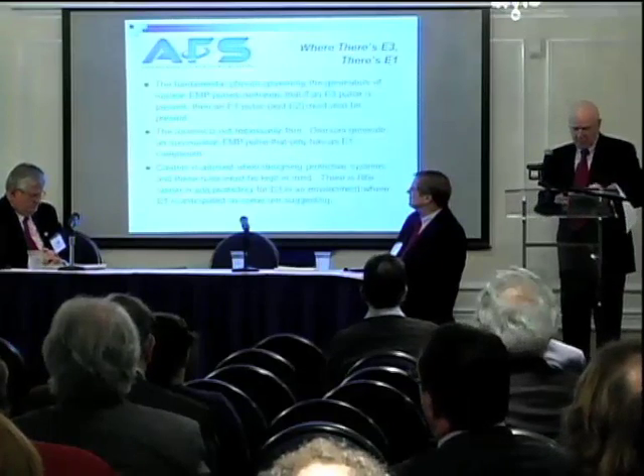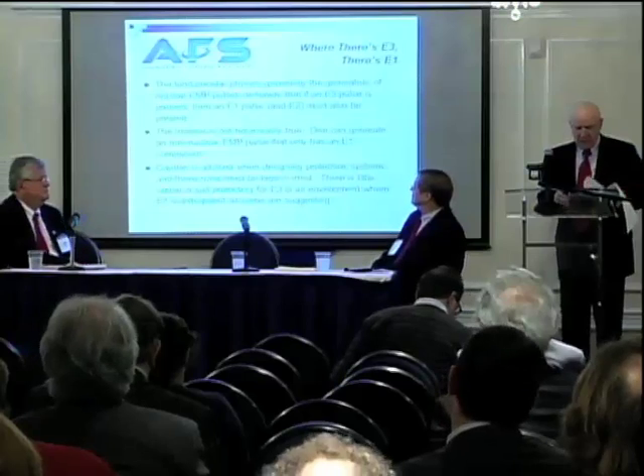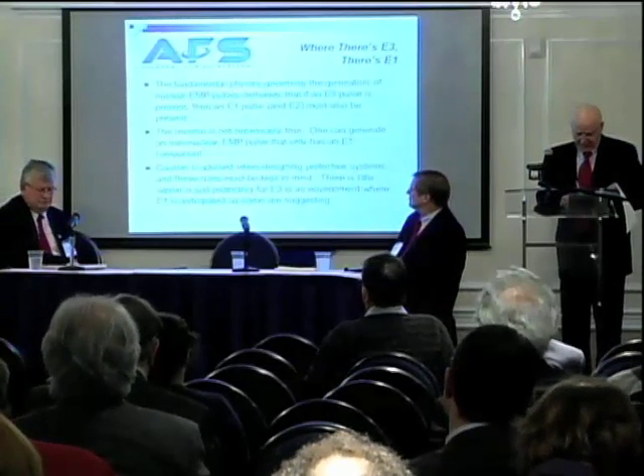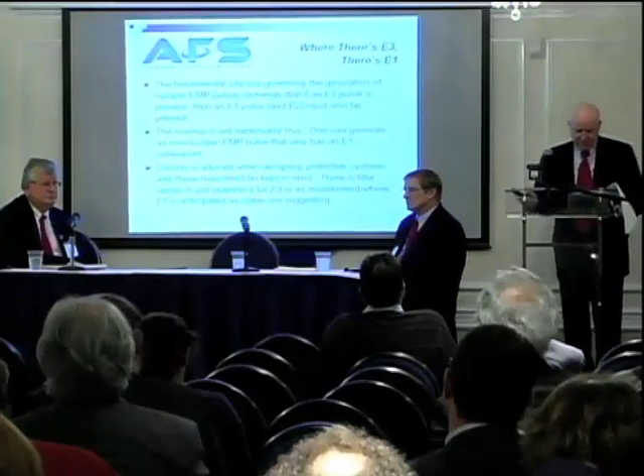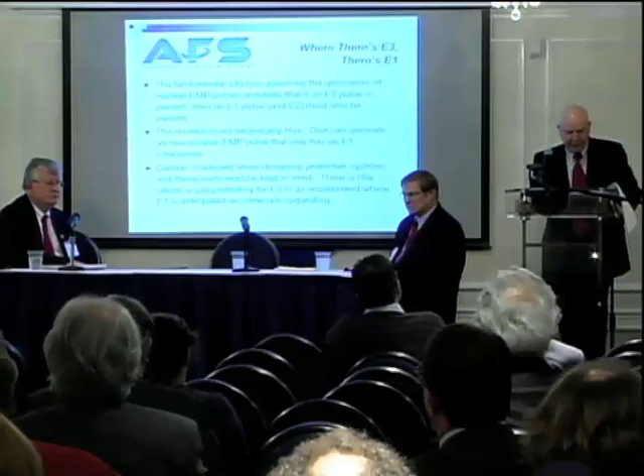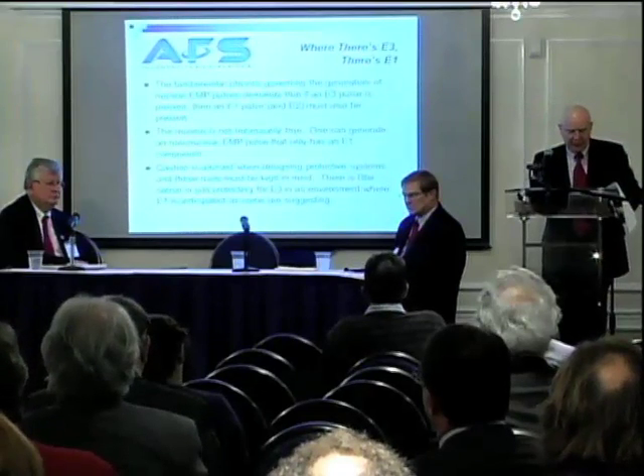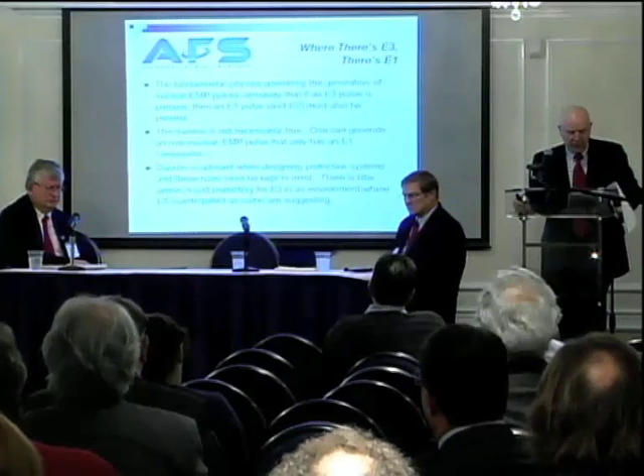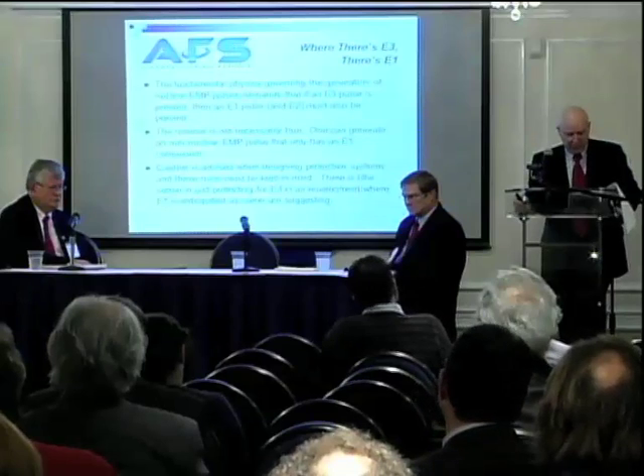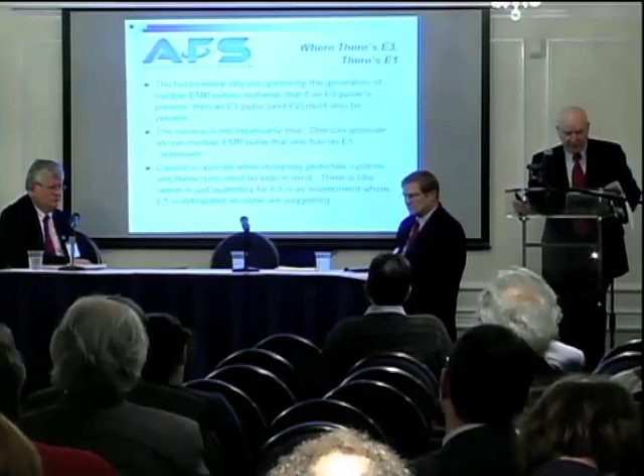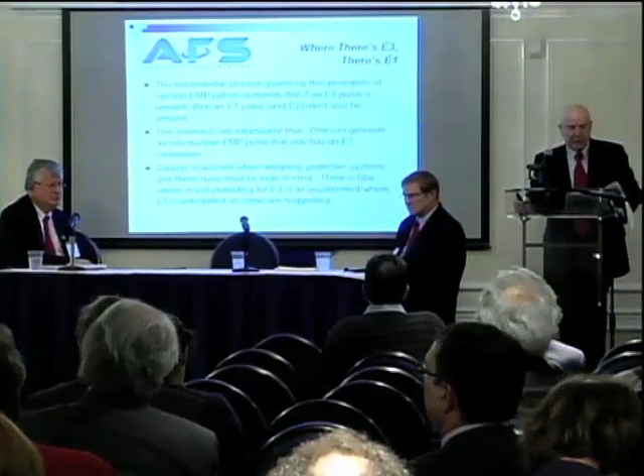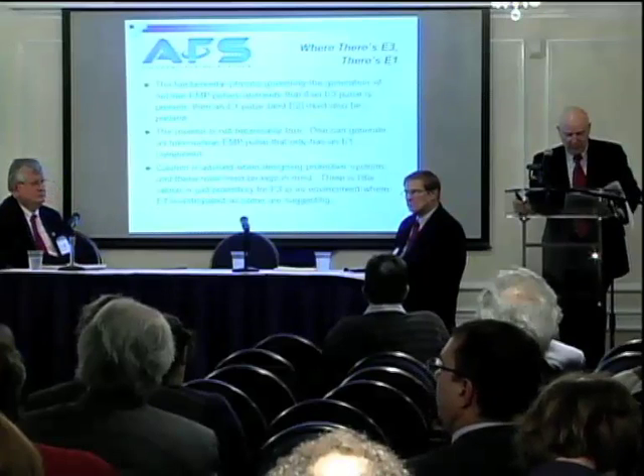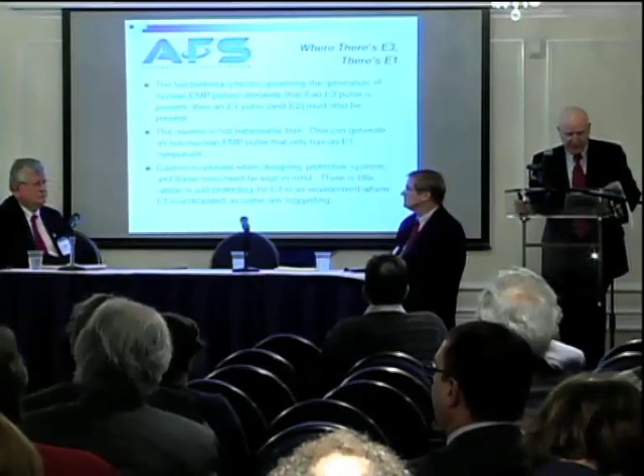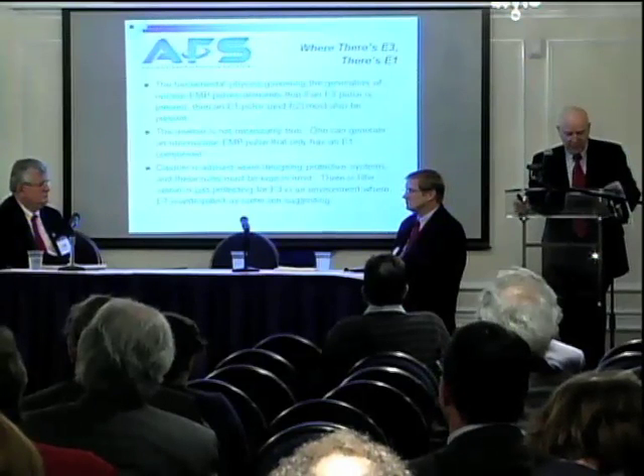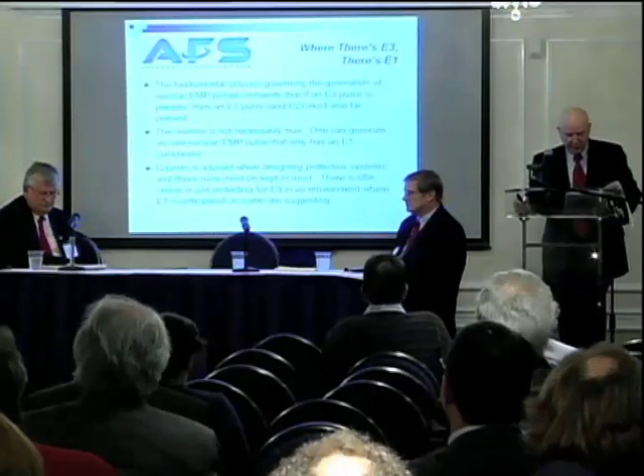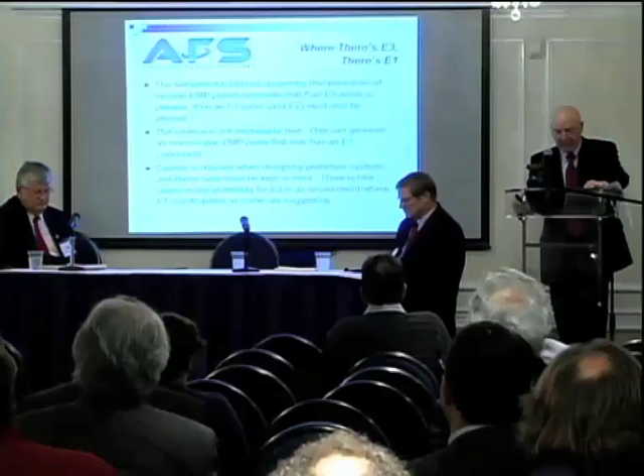Just a word about what we're protecting against. If you're going to have a nuclear event, the fundamental physics governing the generation of the EMP pulse demands that if an E3 pulse is there, both an E1 and E2 will also be present. The reverse is not necessarily true. One can generate a non-nuclear EMP pulse that only has E1. So caution's advised if you're designing a protective system. There's little sense in protecting just for E3 in an environment where you're expecting E1.